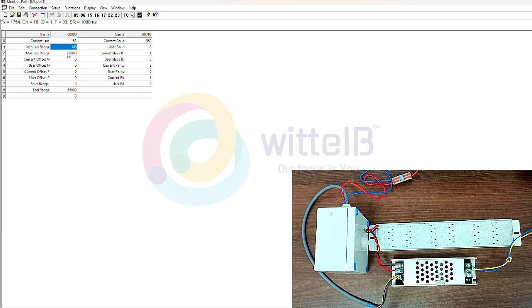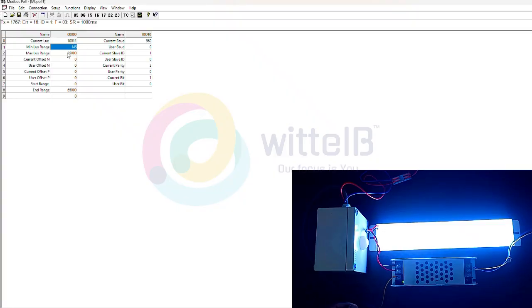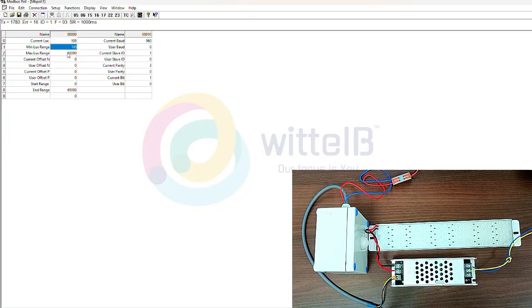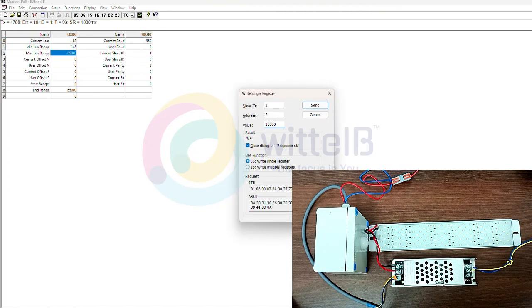Now at the max Lux range, we need to calibrate. For that we need to find out which is the max Lux range. So I will disconnect the device. Here the LED is turned on, and currently I am getting a Lux value of 10,800. This is my maximum Lux range, so I will do the calibration with the maximum as 10,800.